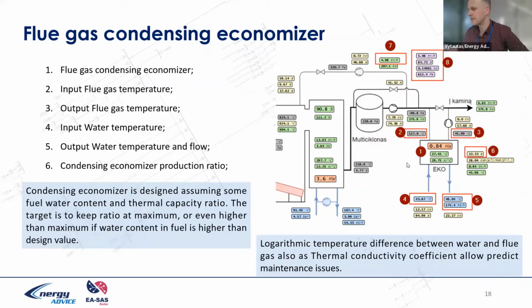Another example is a simplified scheme of a flue gas condensing economizer. Here we have the flue gas condensing economizer, with flue gas input temperature metered from the SCADA, and output flue gas temperature. We have input water temperature, outgoing water temperature, output water flow, and the economizer ratio, the production ratio. I mean, economizer megawatt yield divided by boiler thermal yield. It is a ratio. And of course, we monitor kilowatt electricity per megawatt heat consumption.